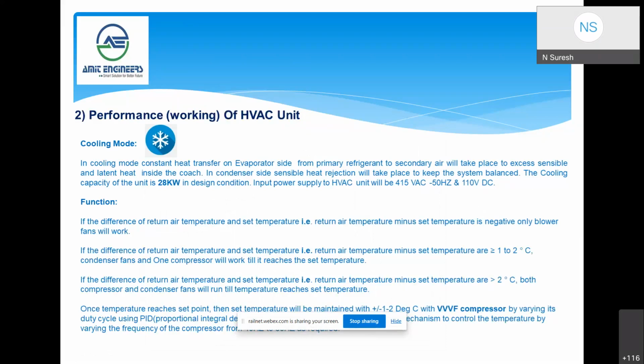These are all the cooling modes, and the cooling mode is set based on the set temperature. When the return air temperature minus set temperature is greater than or equal to 1 to 2 degrees Celsius, condenser fans and one compressor will work till it reaches the set temperature. If the return air temperature minus set temperature is greater than 2, both compressor and condenser fans will run till the temperature reaches the set temperature.